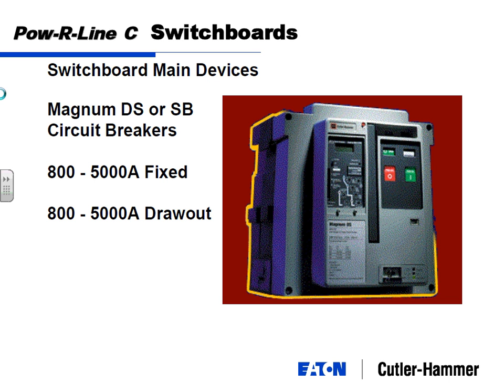The primary difference between a switchboard and switchgear is a switchboard is rated, tested to only 3 cycles. When UL comes in with their standards, there'll be different testing requirements that UL will put on switchboards and switchgear. Switchboards, recall that picture, everything's open. There's no barriers, or there doesn't need to be any barriers between anything, so it's much more cost effective. So the circuit breakers, the molded case circuit breakers, could be stacked up one on top of each other. So if one circuit breaker blows up, you're probably going to take out the circuit breakers next to it in some regard or another.